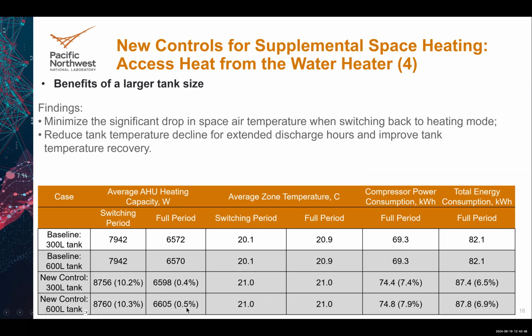So here is the table, basically all the results from the figure. You can see it's around 1 Celsius improvement during the switch period. If you consider the full period, 24 hours, the total energy consumption increase is less than 7%. So that's the trade-off. I mentioned if you want to improve your actual heat transfer rate, then you need to consume more energy, but this consumption is less than 7%.